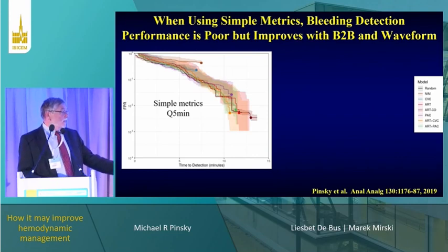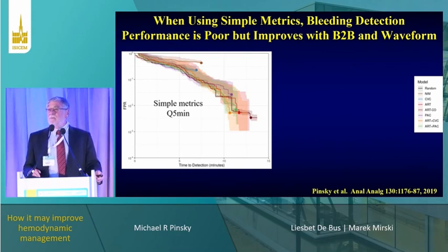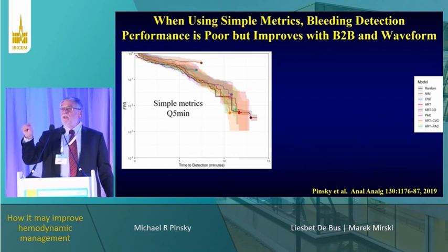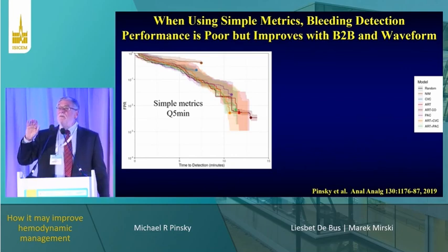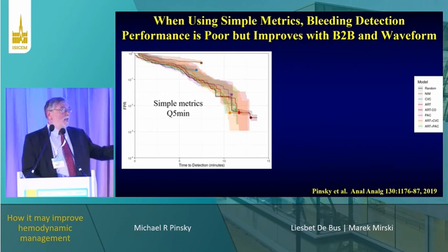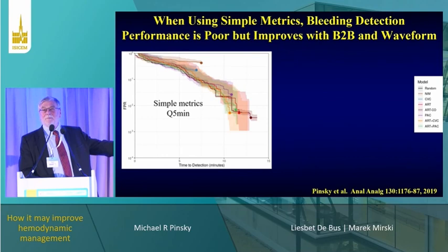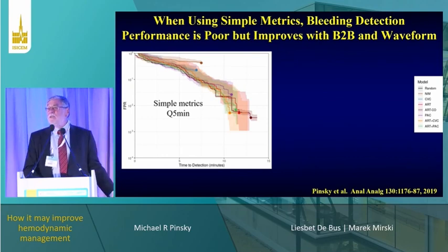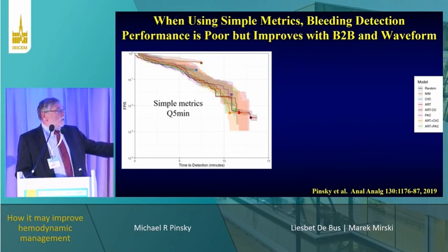Now what you'd like to have is, as soon as the event happens, the machine goes off, and there are no false positives. What do the machines in your hospital do, the monitors? They're sensitive all the time. If you want to not miss a single time, have the monitor going off continuously, because once there's an instability, the monitor will still be positive. But that's meaningless, and that causes alarm fatigue, but that's what we have today. So what you want is a low false alarm rate, and this is the log scale. This is 1 in 10 times it's wrong, 1 in 100 times, 1 in 1,000 times.